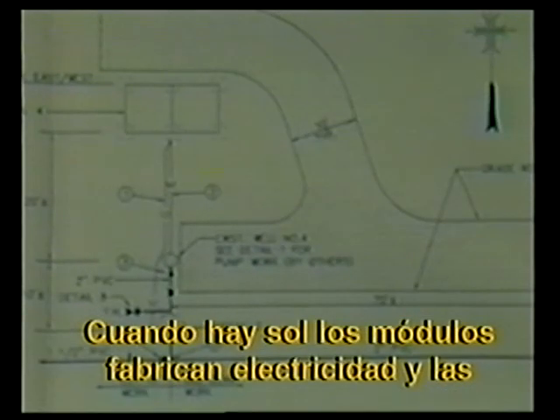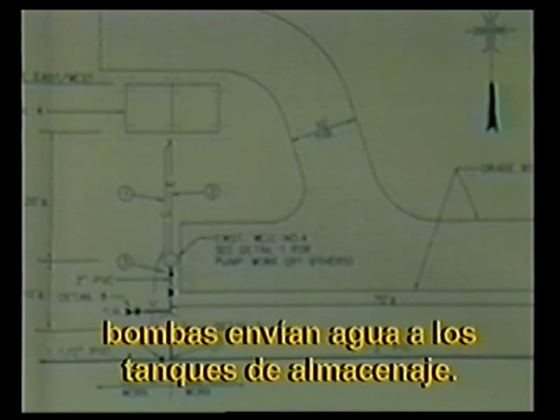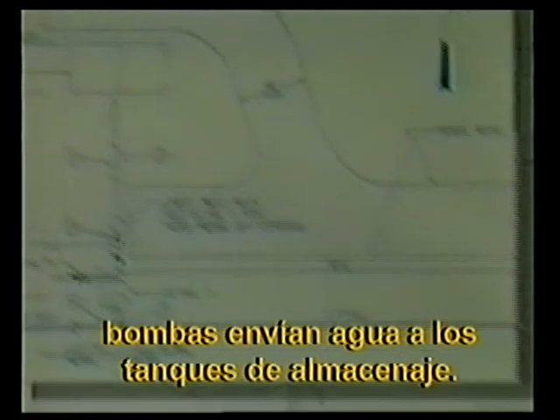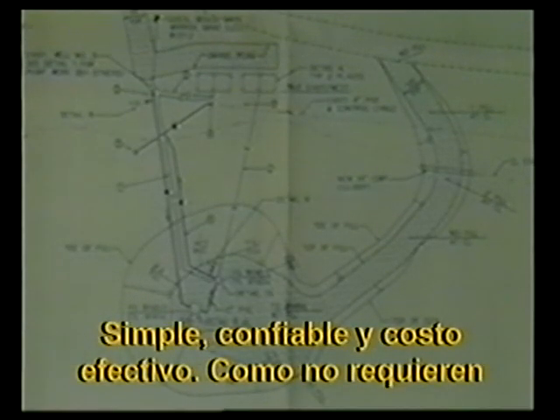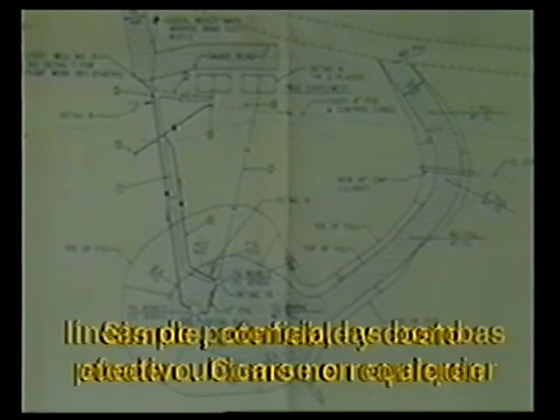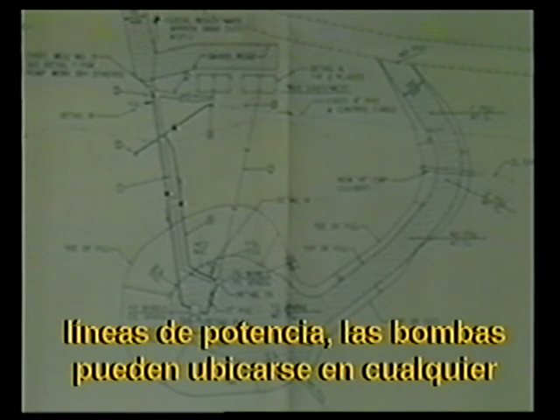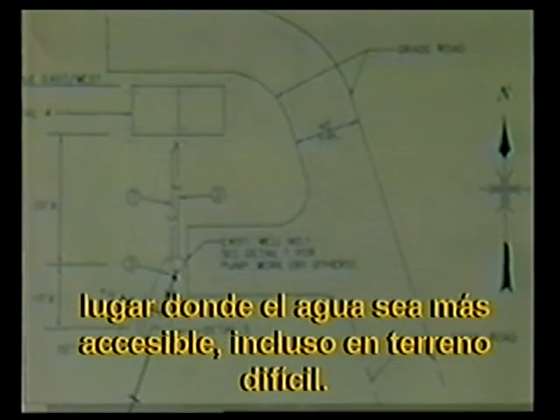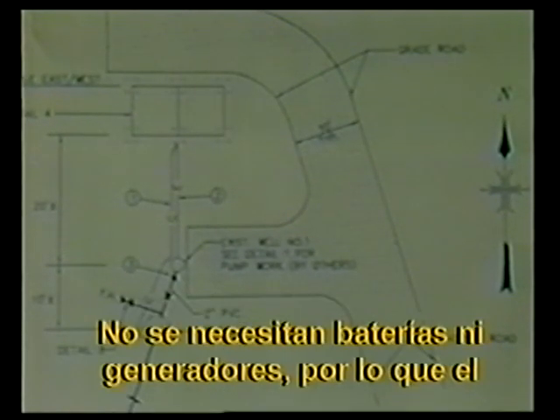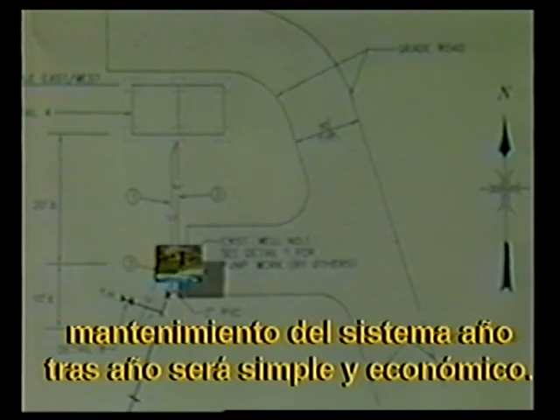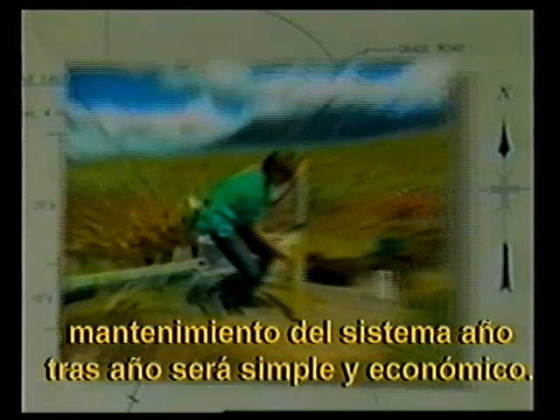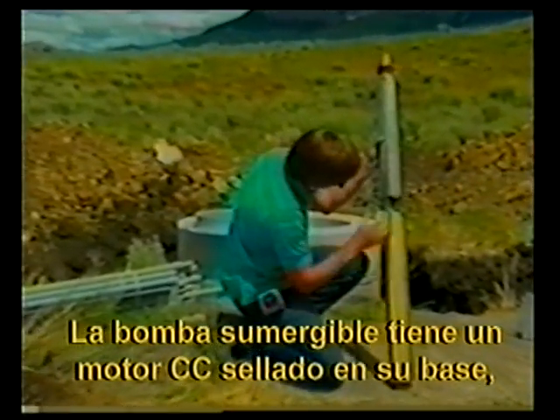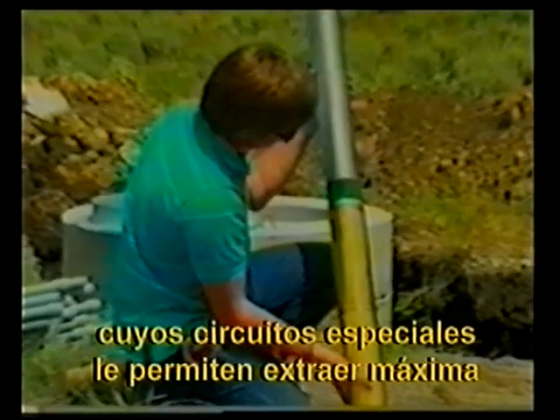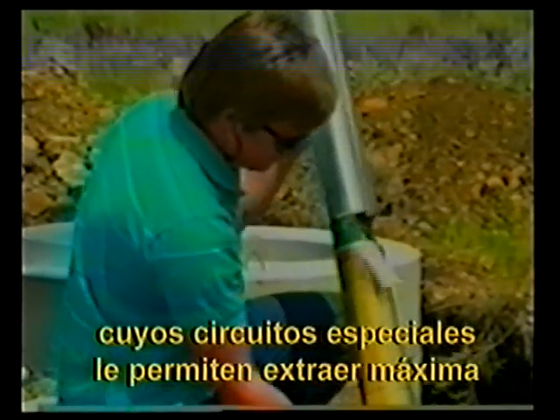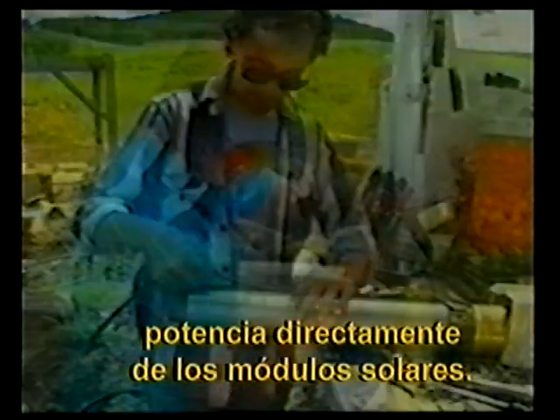When the sun shines, the modules make electricity and the pumps deliver water to storage tanks. Simple, reliable, and cost-effective. Since no power lines are needed, the pumps can be located wherever water is most accessible, even in difficult terrain. No batteries or generators are required, so maintaining the system year after year will be simple and inexpensive. The submersible pump has a sealed DC motor at its base with special circuitry that allows it to draw maximum power directly from the solar modules.